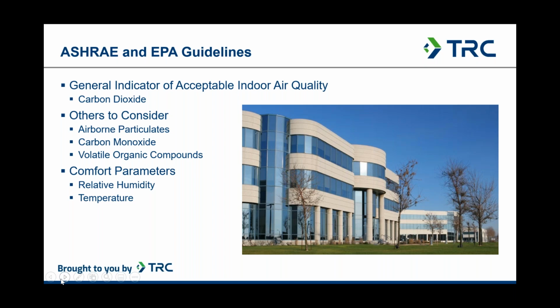The next parameter, airborne particulates. So if we measure airborne particulates, both the size and concentration, it gives us an idea of the relative effectiveness of the filtration or a local particulate generation source. The next parameter, carbon monoxide. Since carbon monoxide is a byproduct of combustion, it can be from outdoors, such as vehicles, smoking, or fires, which are entrained into the building by the outdoor air intakes or negative pressure of the building. There also can be indoor sources, such as improper venting of a gas-fired appliance, hot water tank, or gas-fired air handling units. This is a good parameter to check in these COVID times, because buildings are often shut down for extended periods, and you want to make sure that these combustion sources are properly ventilated.